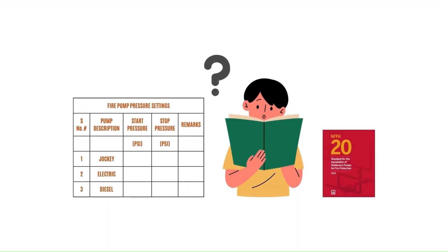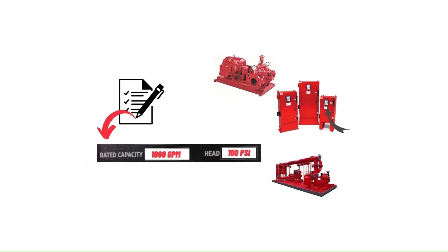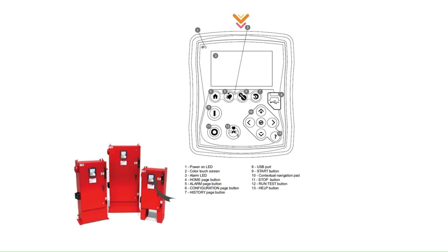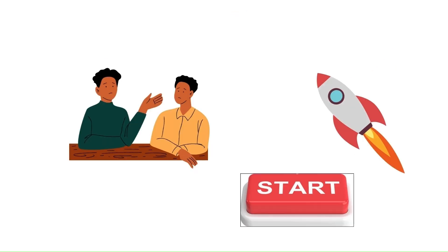Before we attempt to determine the pressure settings for NFPA 20, we need to fetch the data related to the selected fire pump. The manufacturer will provide factory preset settings; however, these settings can be adjusted from the pump controller at the project site, so we could potentially increase or decrease the range based on our requirement. Let's go ahead and start determining the stop and start pressures of the fire pump.